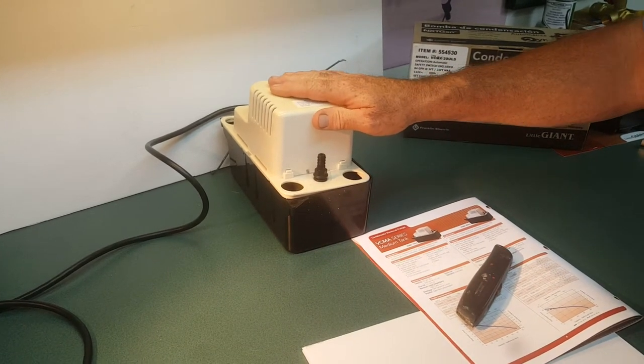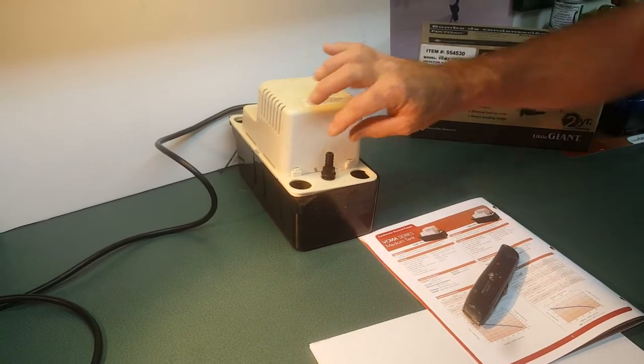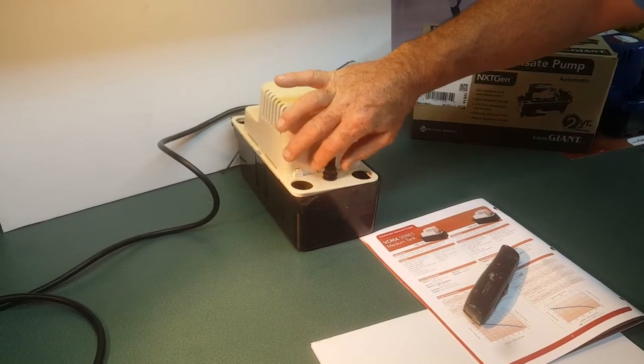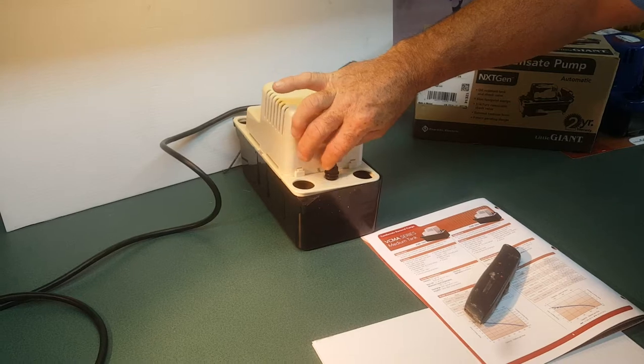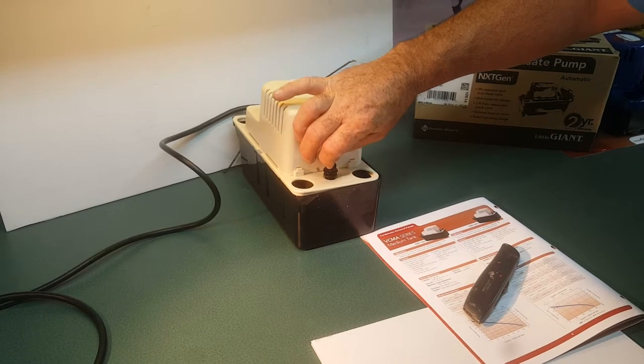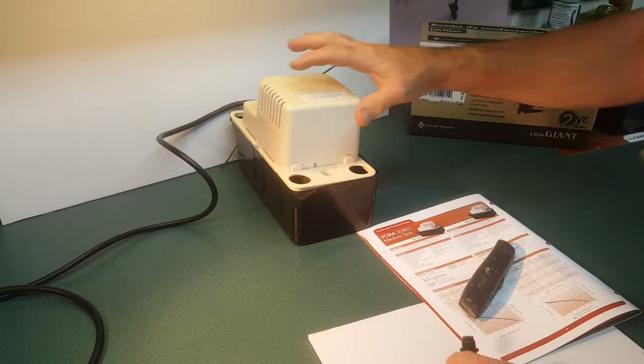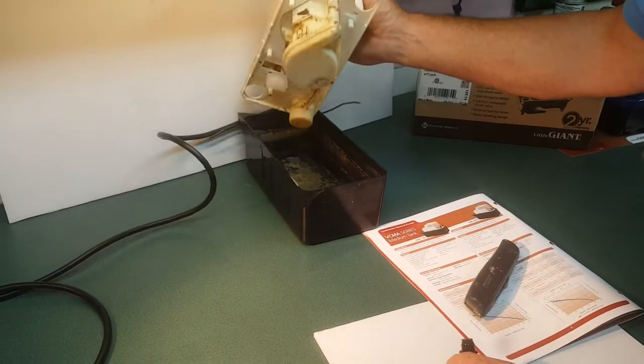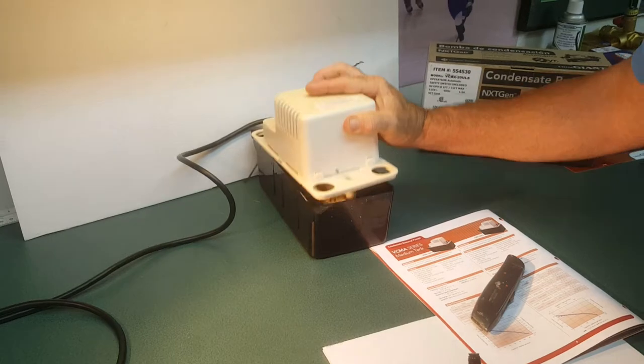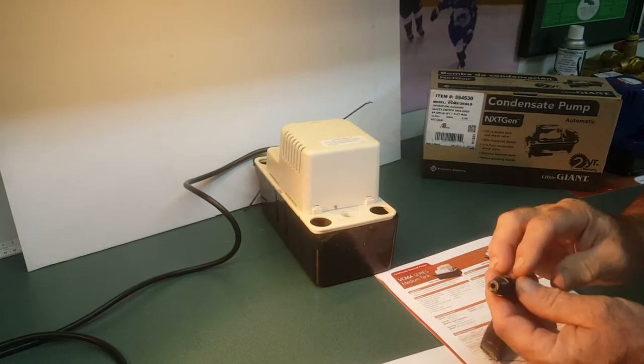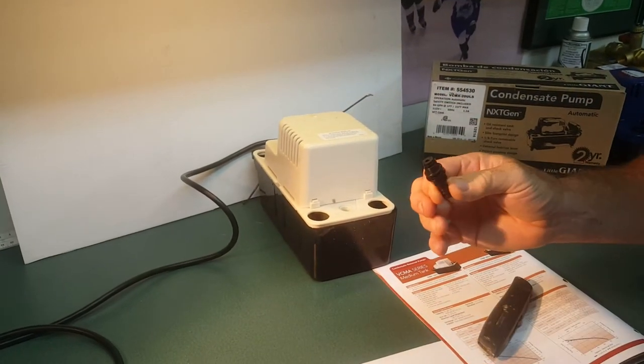This is a VCMA series Little Giant condensate pump that was returned under warranty because it wasn't pumping. But after looking at it, we found that the pump is really dirty and a lot of that dirt had collected in the check valve.